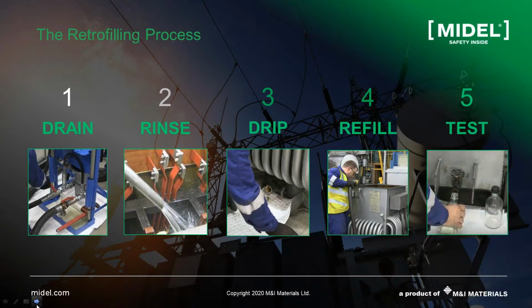If you measure the tan delta of the transformer, in this case you will get a little bit higher, sometimes double the number you get with mineral oil. And again, that is due to the chemistry of the ester liquids. There is no issue with that. Everything is perfectly fine. Just please be aware of that. And if everything is okay, after the refilling, when you have done all that job, changed the cartridges, changed the filters, all the things, you are able to energize the transformers and bring them on load. So now I'd like to hand back over to Steve, and he will show you some case studies.